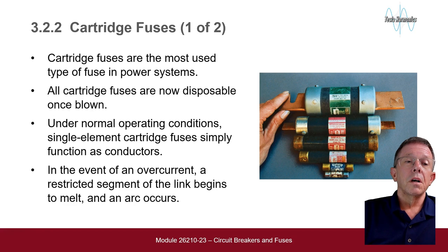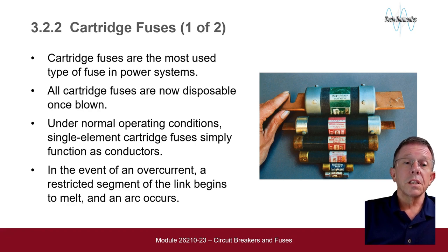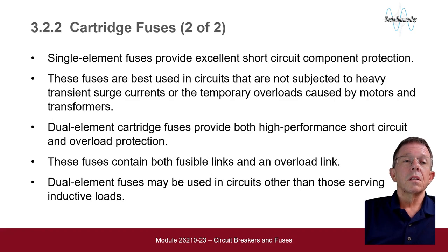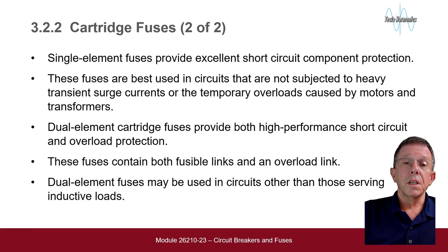Cartridge fuses are the most used type of fuse in power systems. All cartridge fuses are now disposable once blown. Under normal operating conditions, single element cartridge fuses simply function as conductors. In the event of an overcurrent, a restricted segment of the link begins to melt and an arc occurs. Single element fuses provide excellent short circuit component protection and are best used in circuits not subjected to heavy transient surge currents or temporary overloads caused by motors and transformers.